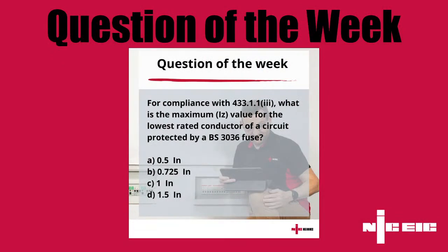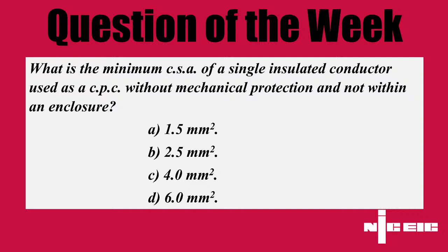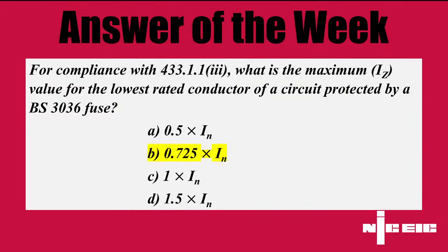Question of the week this week was around current carrying capacity, and when we come to find out what our current carrying capacity of our cable is for compliance with 433.1.1 indent 3, what's the maximum Iz value for the lowest rated conductor of a circuit protected by a BS 3036 fuse? So BS 3036 fuse, quite commonly termed as rewirables. We gave you four options. Is it 0.5 times the nominal rated value, 0.725 times the nominal rated value, 1 times the nominal rated value, or 1.5 times the nominal rated value? When I looked at the polls earlier today, we had 70% of the people with the right answer, which was good to see, and that right answer is 0.725 times the rated value.